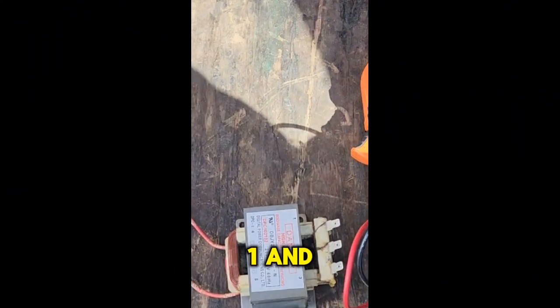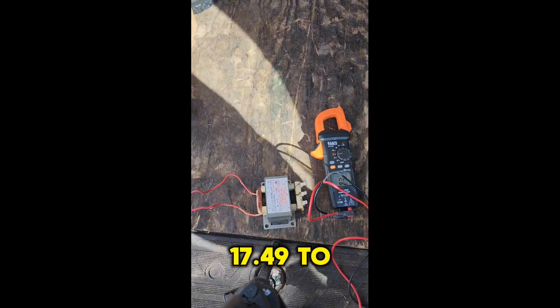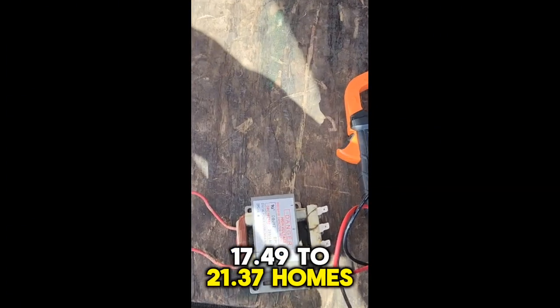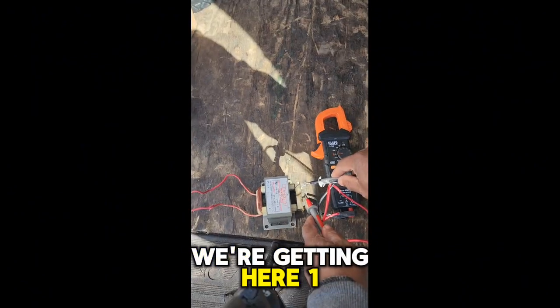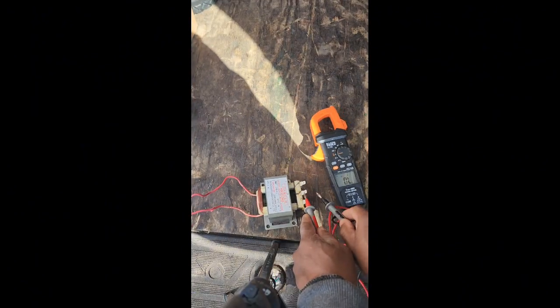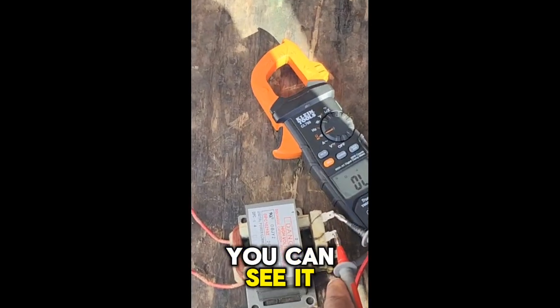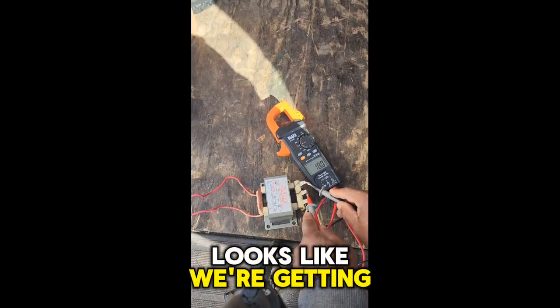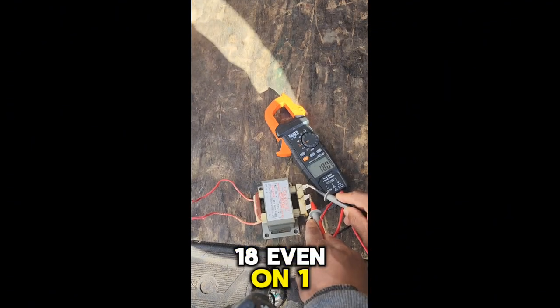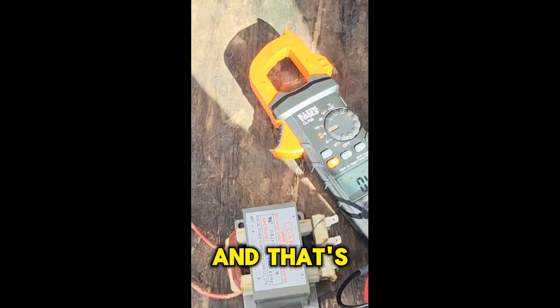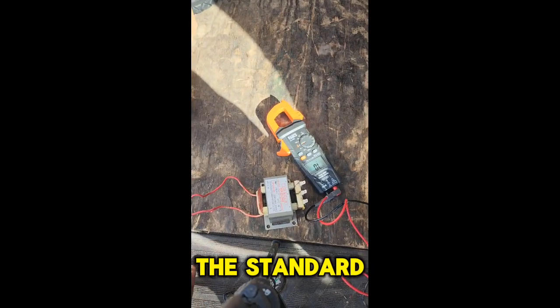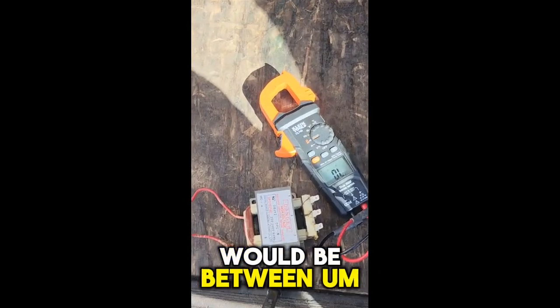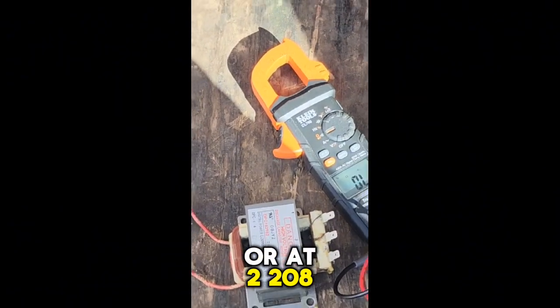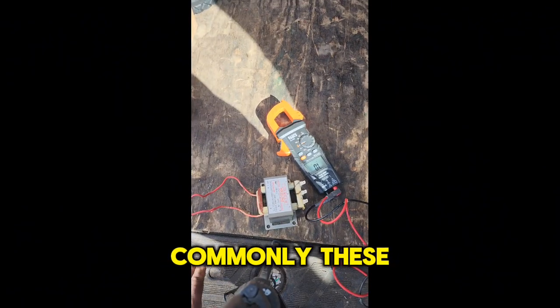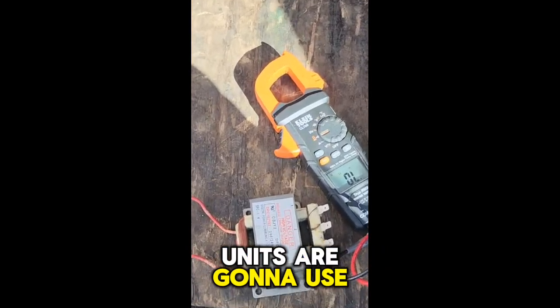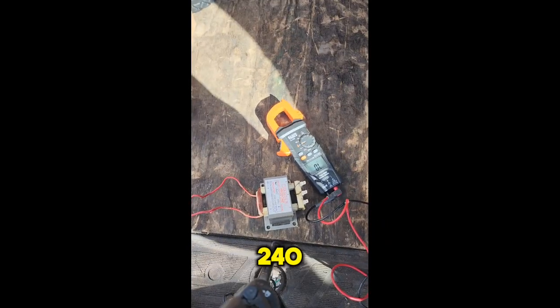For terminals number 1 and 2, you should get between 17.49 to 21.37 ohms. So let's see what we're getting here. 1 and 2. Let's put it so you can see it. Looks like we're getting 18 even on 1 and 2. And that's for the standard in the US, which would be at 208 volts. So commonly these TurboChef units are going to use the 208 volts. Some will use the 240 volt.